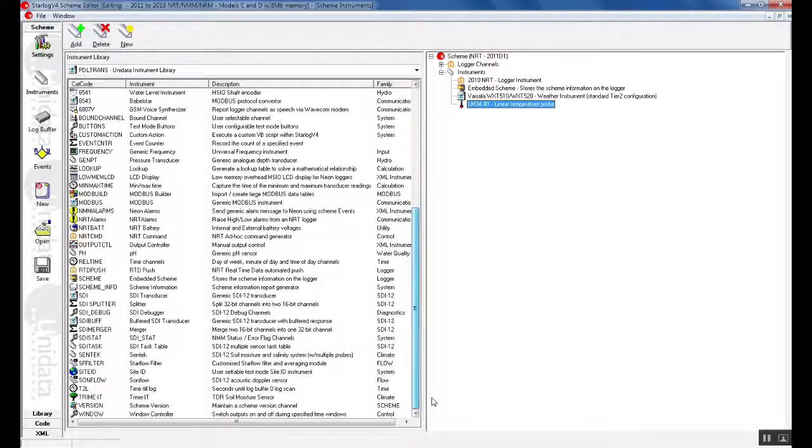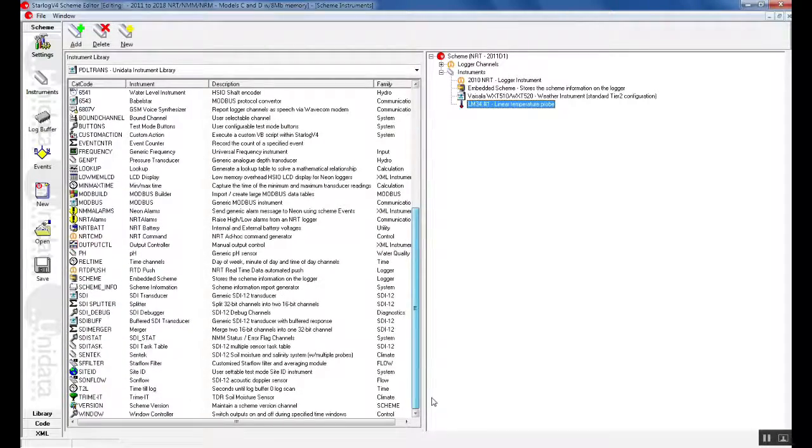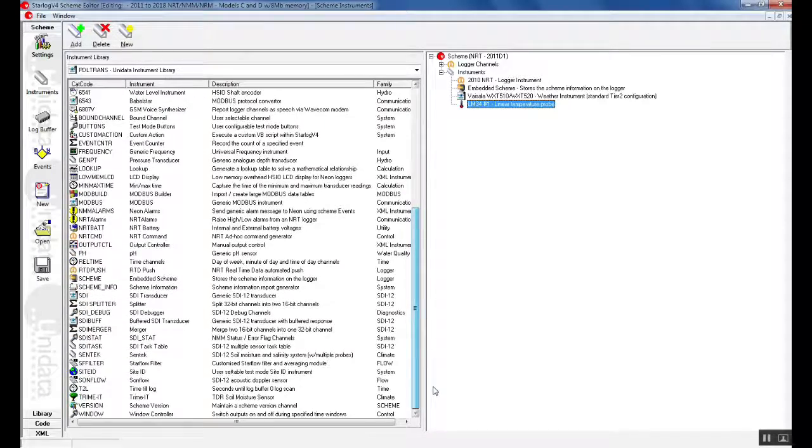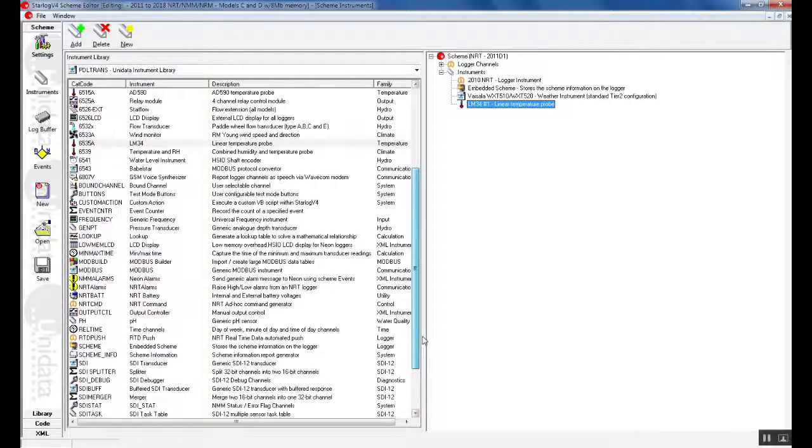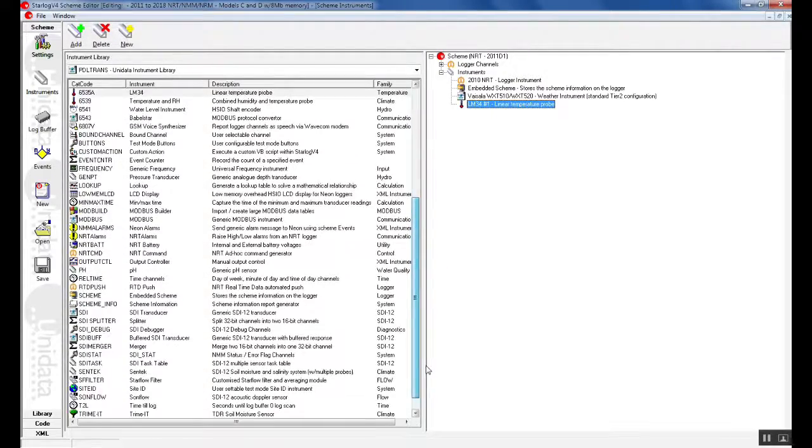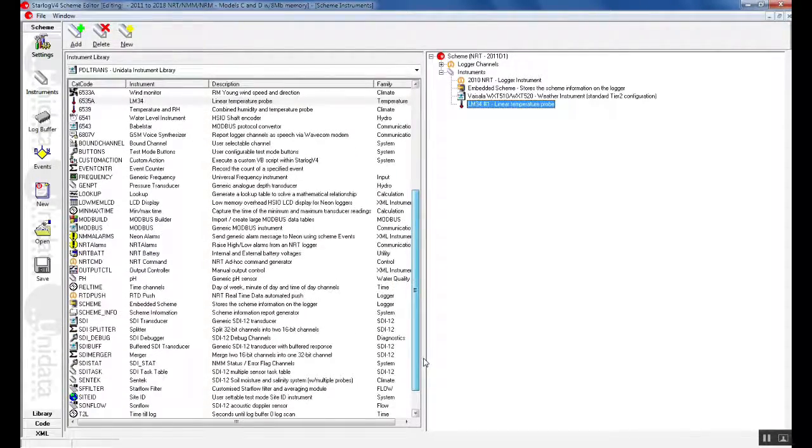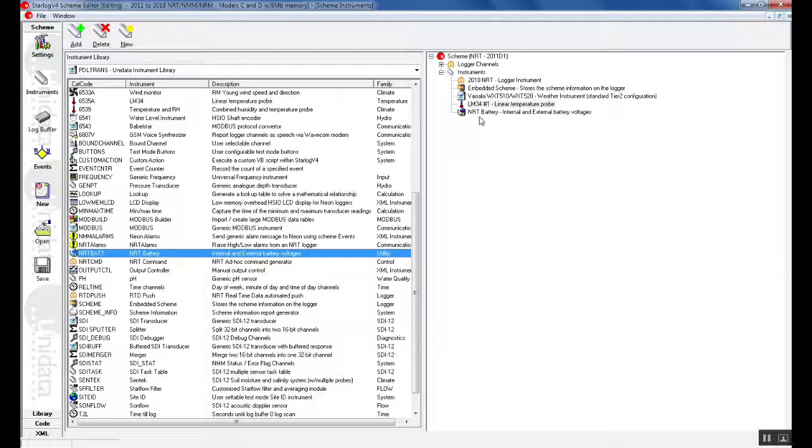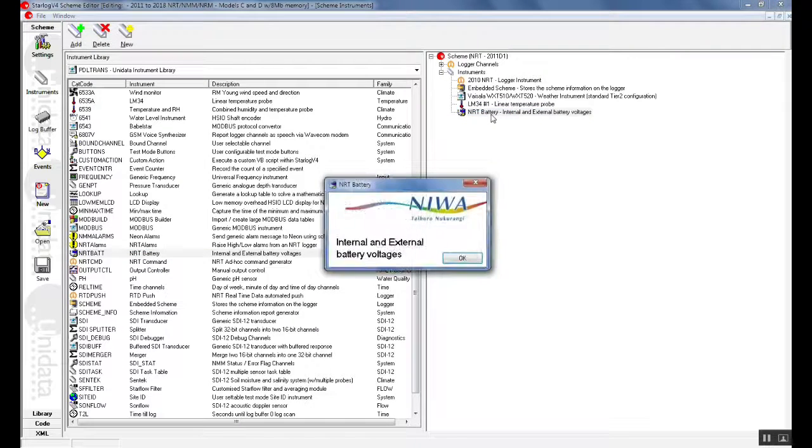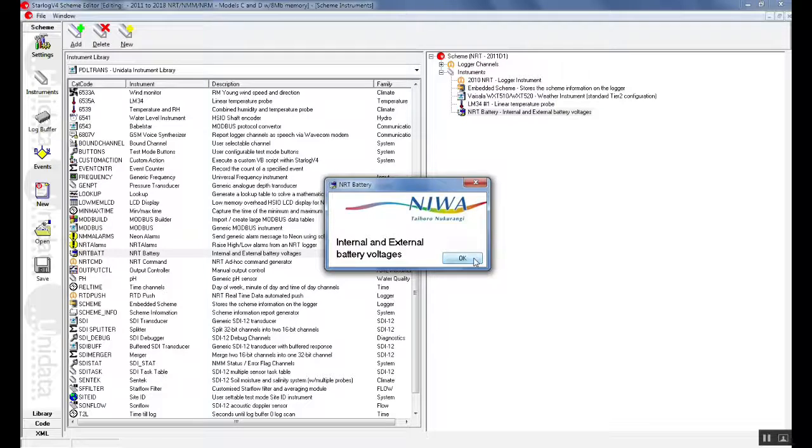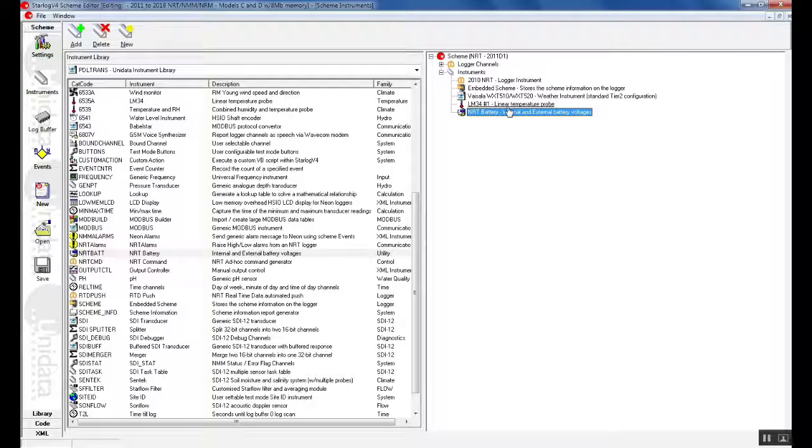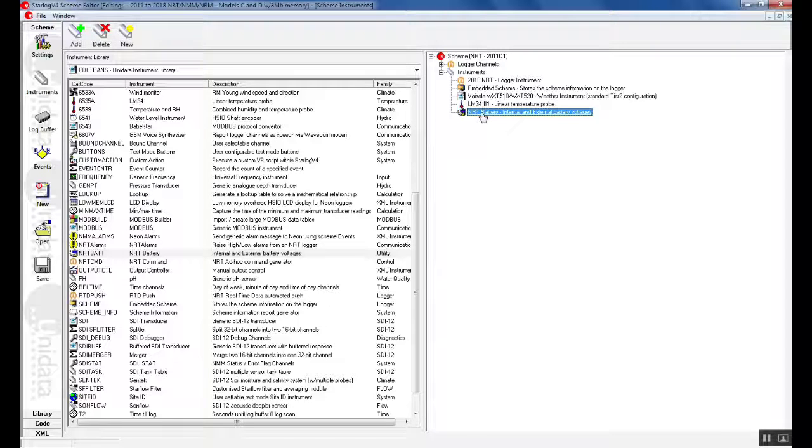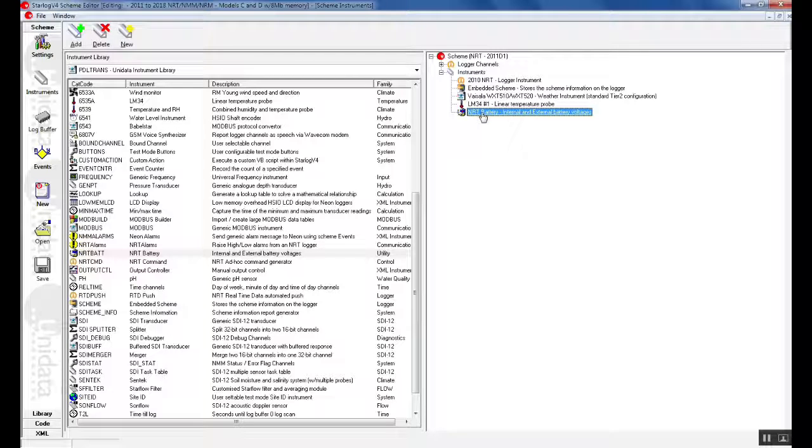In our NRT scheme we always also tell the customer to record the battery voltages as these are critical when checking NEON and checking if the current battery voltage is good or not good as this is a main concern when the units are placed in the field. To select the battery we can click on the NRT battery. This is automatically added and there is no need to change anything here. When we click on it it will just say that we have added the internal and external battery voltages. We can click OK here. So this scheme now contains a weather station, a temperature sensor and for us to record our battery voltages which are connected to the NRT.